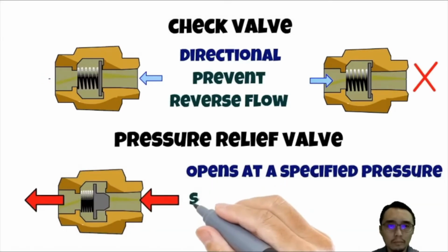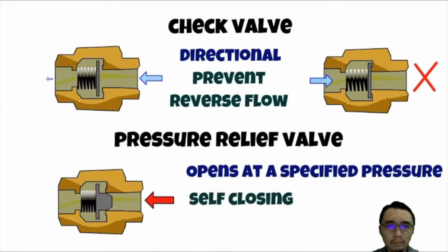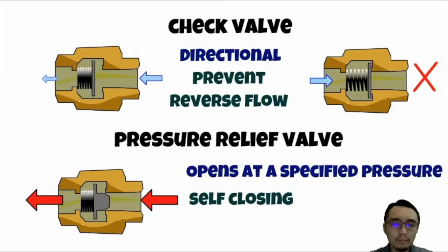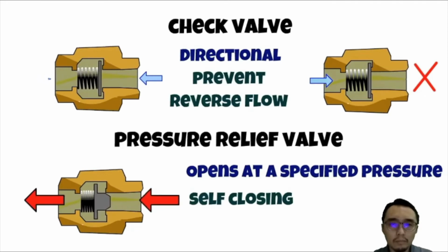The spring compresses till the seal is pushed past the sealing chamber, and then pressure is released until the spring overpowers the pressure and reseals the valve. These valves have saved lives by keeping operating pressure within safe range. And the best part of a relief valve is that the failure occurs at the seal. And when that happens, the relief valve just prevents any pressure from building within the system. So a quick change and you're back up in operation.